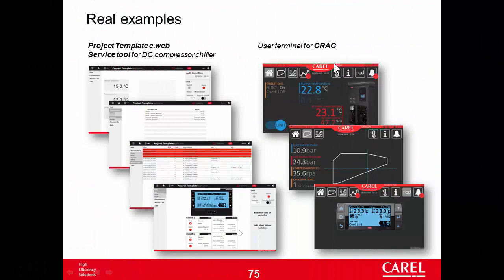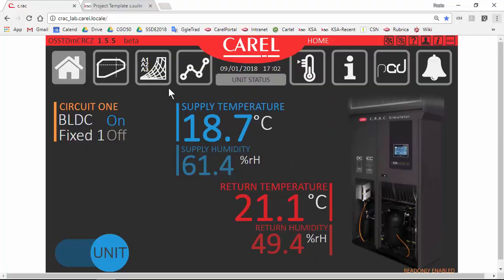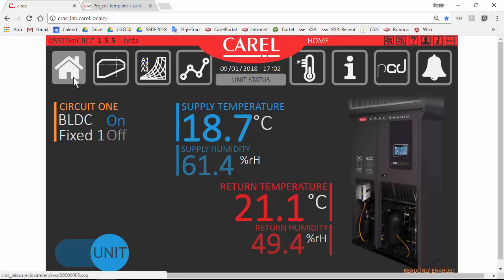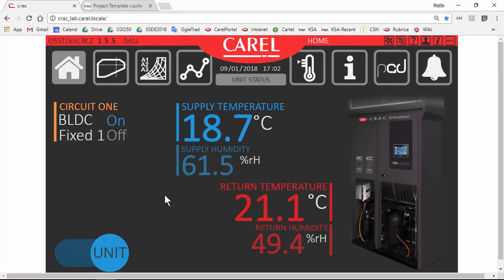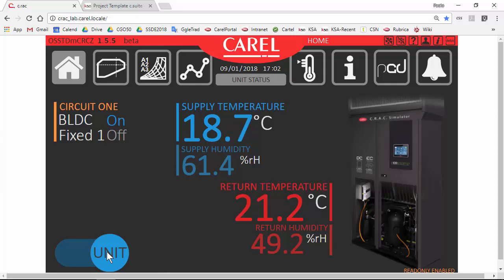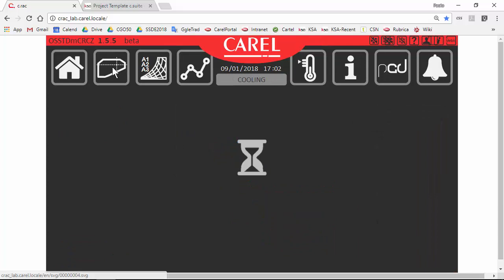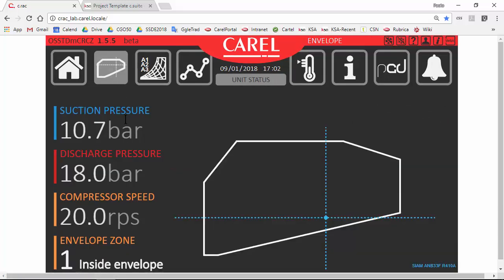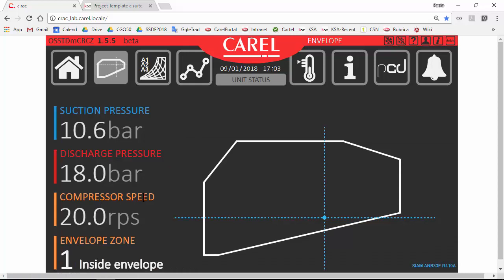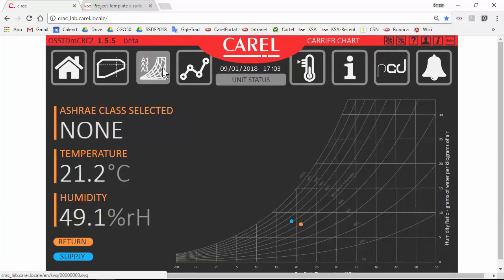The other project that I want to show is the user terminal for a CRAC unit, computer room air conditioning. This is a real application, a real unit in our product development office. Also in this case, I don't want to go too much in the details. We have a home, this page with the main temperature. Actually, I can't switch off, switch on the unit because it is in read-only mode. So I can't modify parameters. I can only see. Here is the envelope of the compressor. You can see that the compressor is at minimum speed. Psychrometric diagram. Temperature humidity looks good.